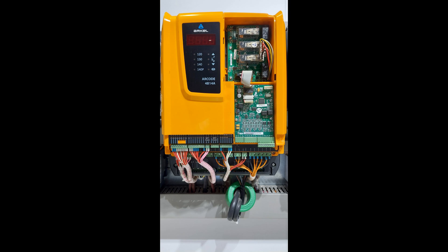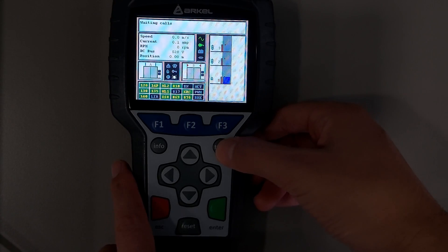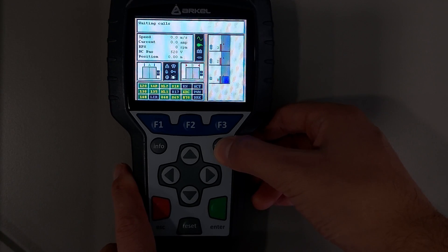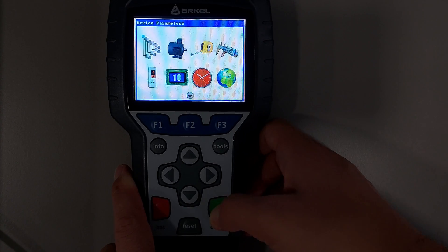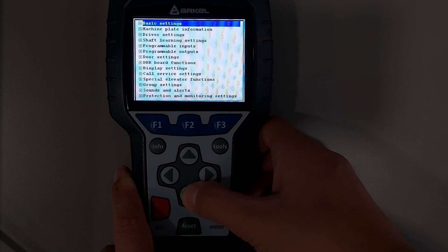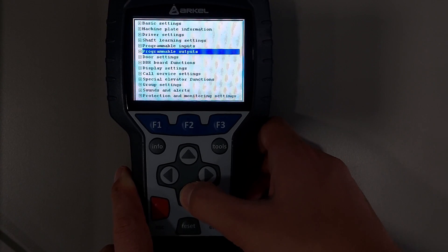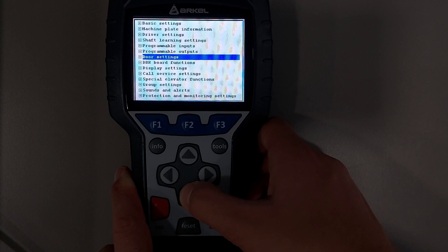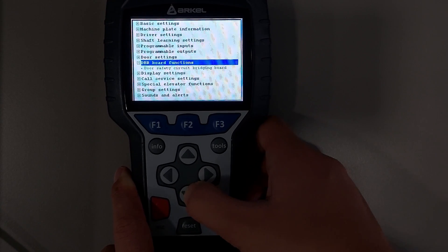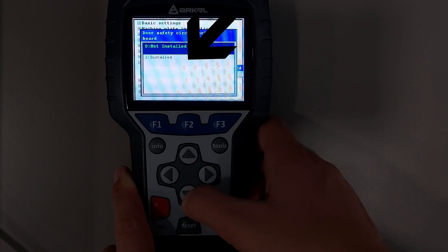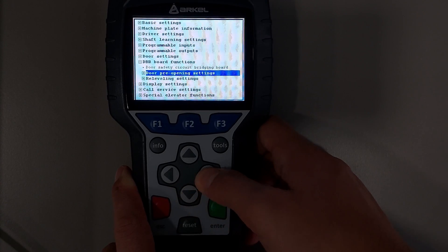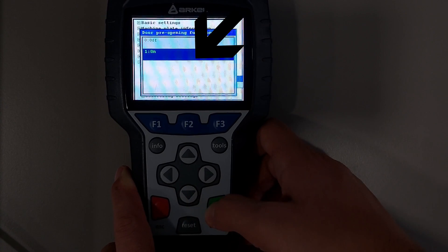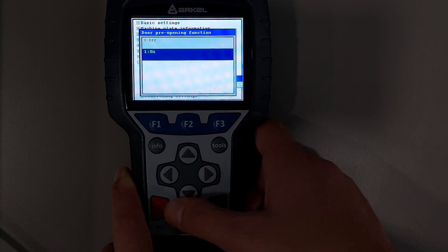Before starting the test, the following parameters should be checked. Press the Tools button then go to Device Parameters. Under DBR board functions, the door safety circuit bridging board parameter should be arranged to installed, and the door pre-opening function parameter should be arranged to on.